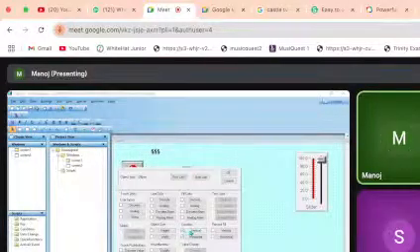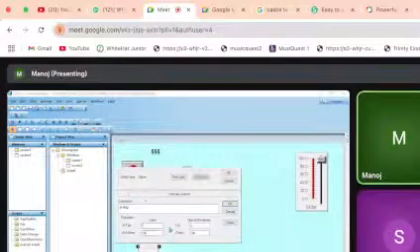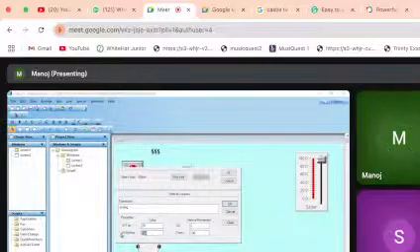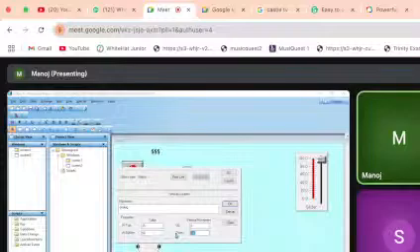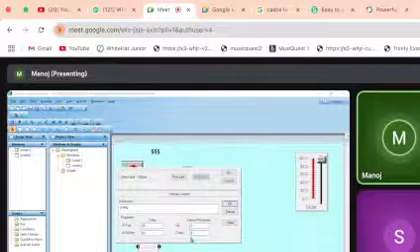So now one more operation we can do, that is vertical movement. Vertical, yeah, that you can select. Here also we can link the tag name. Here minimum value is 25, maximum value is 50. It should move 0 to how much? 210, sir. 210. So I will take somewhere around 250, or else 240 only I will take.